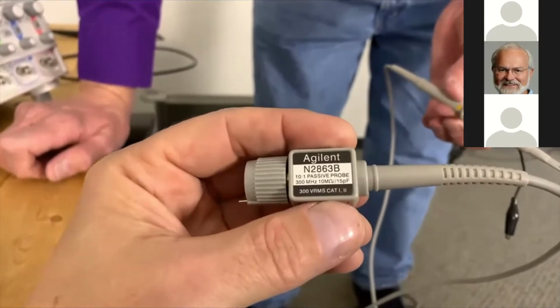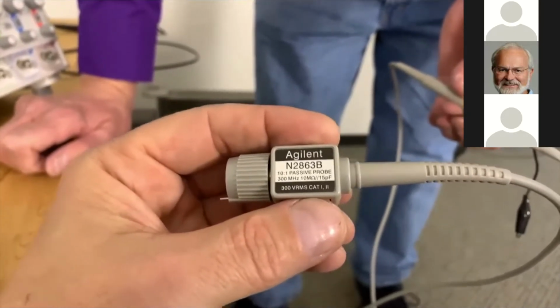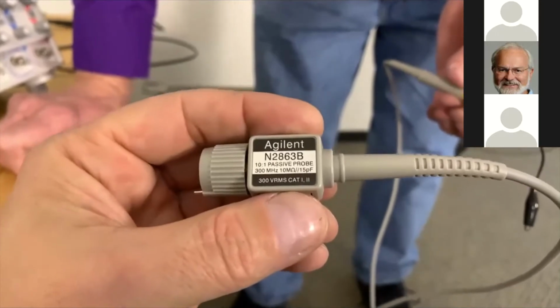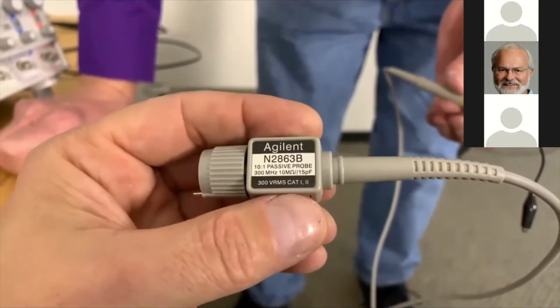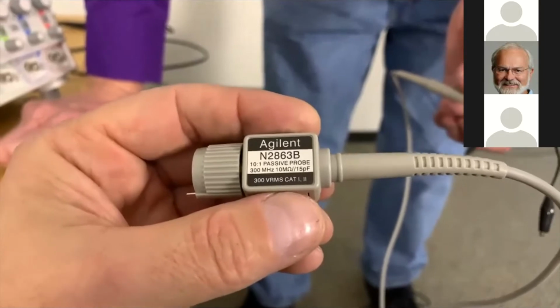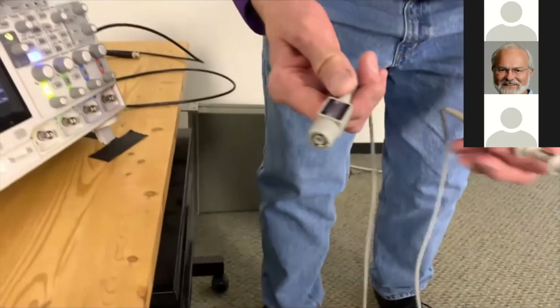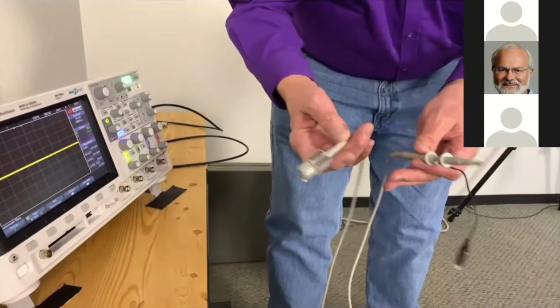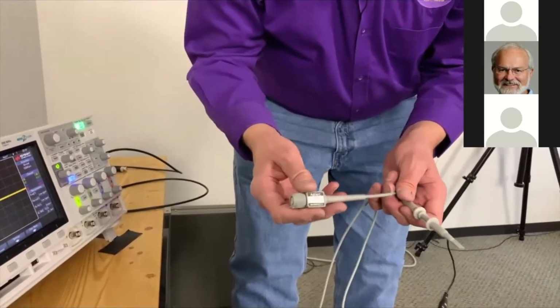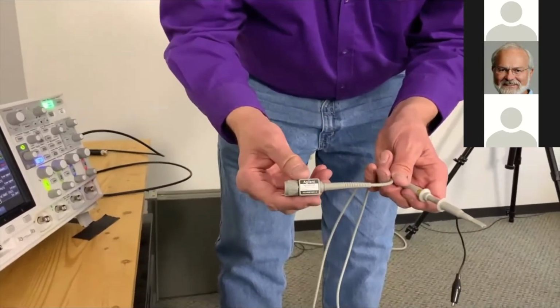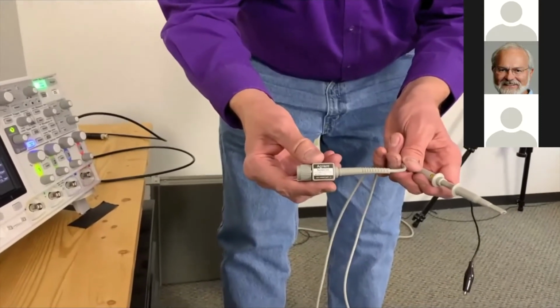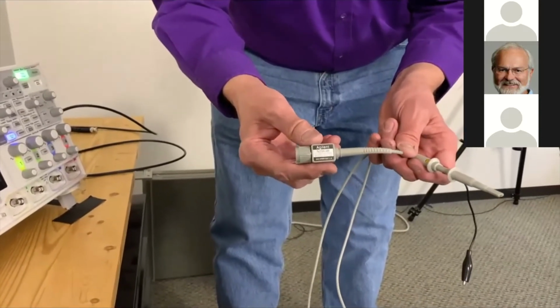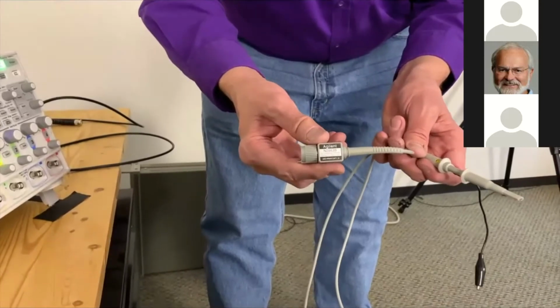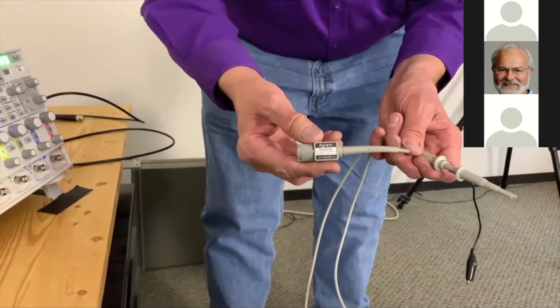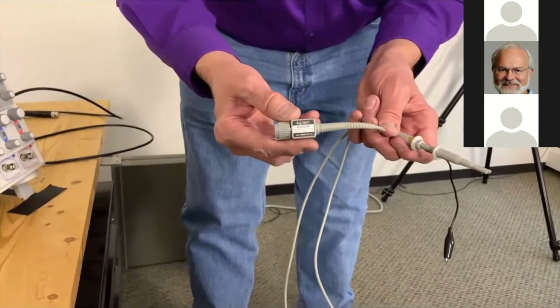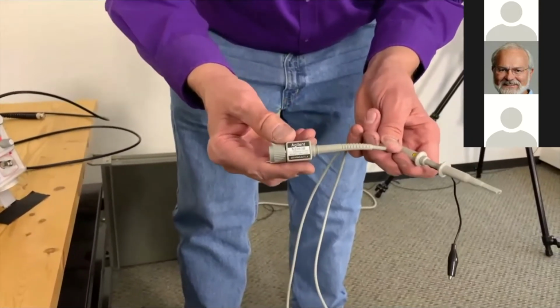This one shows it's a 10-to-1 passive probe, 300 megahertz, 10 megohms, 15 picofarads that it's going to add to the device that you're testing. Okay, so 300 megahertz, that's useful to know. We need to know that it has the bandwidth to handle whatever the rise time of, say, a pulse. This is going to be really important because if the bandwidth is not high enough, then it's going to affect the pulse. It's going to round it off, and we won't get an accurate measurement on that.